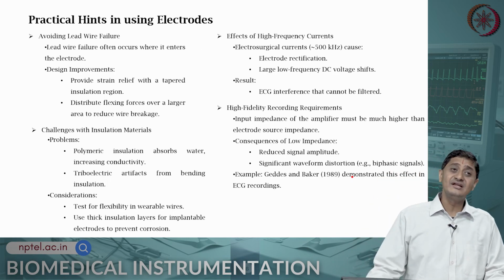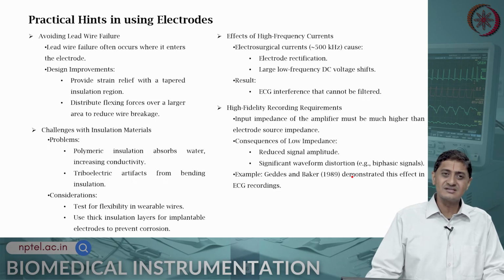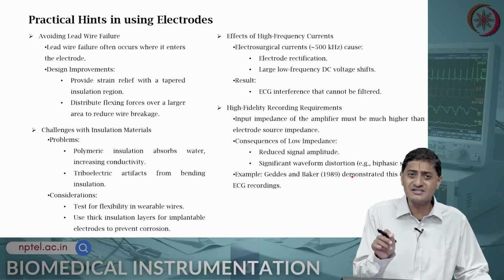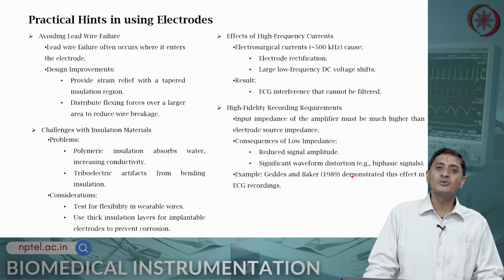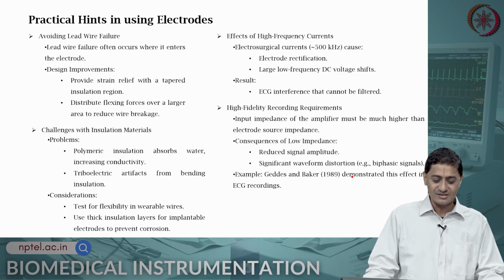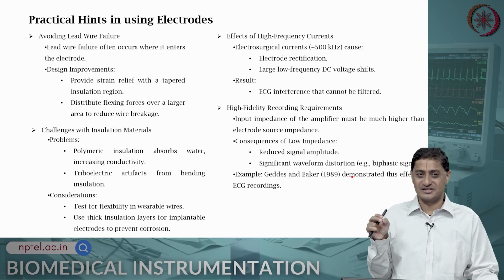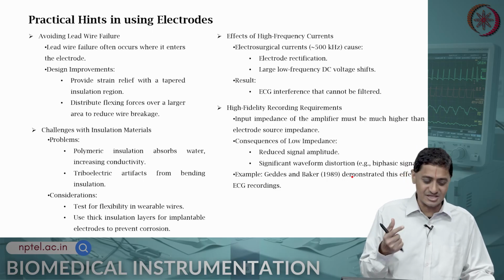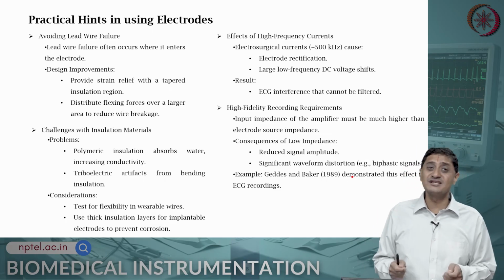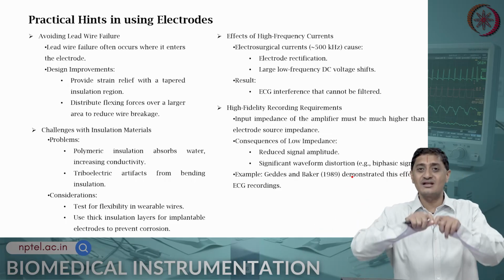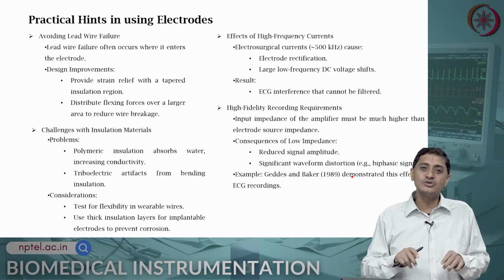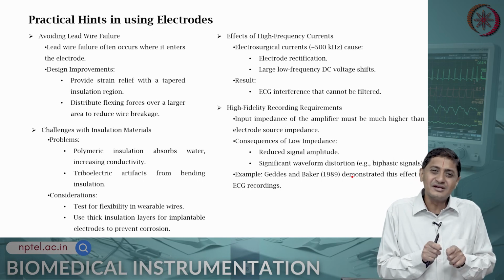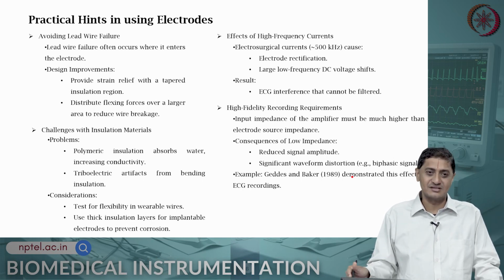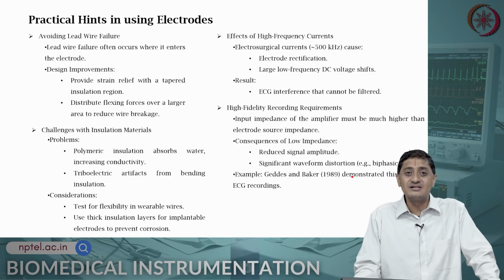The other is avoiding lead wire failure. This happens often because of a mechanical failure. Often what happens is that where the wire enters or touches the electrode, that is where the failure happens. You have to provide strain relief. So, you need to have a tapered insulation region so that sufficient mechanical strength is provided, and distribute flexing forces over a relatively large area or a large bending diameter, to ensure that it is not bent critically at that point so that it breaks. That is a mechanical strength problem.